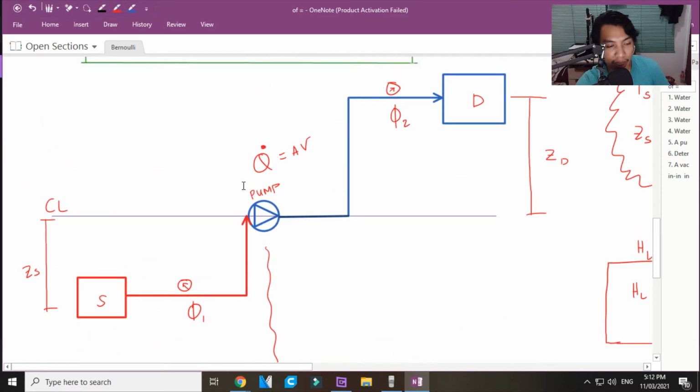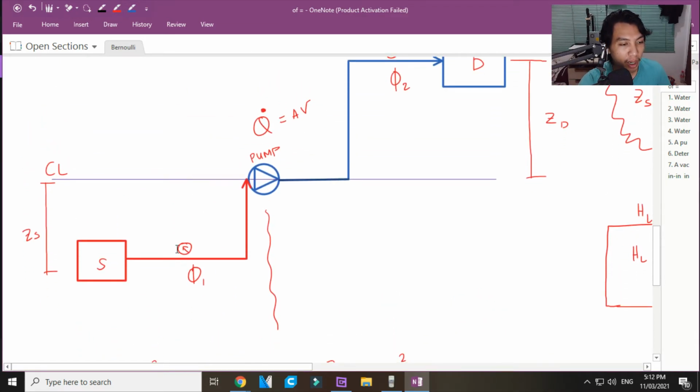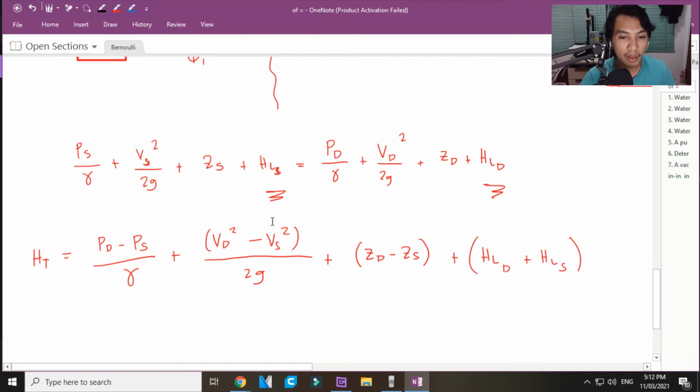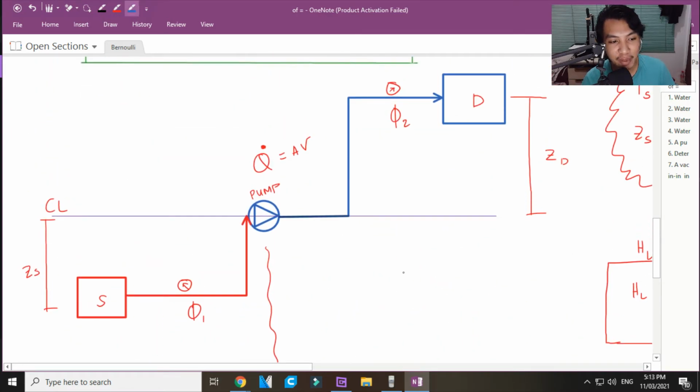Now, pag ganitong case class, ano mayayari? Add mo ba yan or ima-minus mo? Ang sinabi dito, sinabi dyan, ZS is negative if the source is below the pump center line. Ibig sabihin, negative, okay? Negative. That your ZS is minus tapos negative ZS. Yan, magiging positive to. So, ang kalalabasan yan is ZD plus ZS. Bakit sir nangyari? Ang paliwanag dyan, ganito. The explanation there is, yan yung hahabulin ng pump mo na head. Okay? Yung inakyat niya at yung iakyat pa niya. That will be in total.